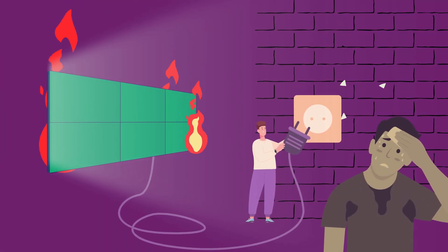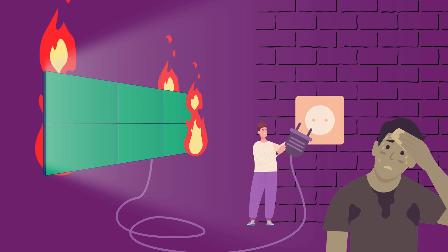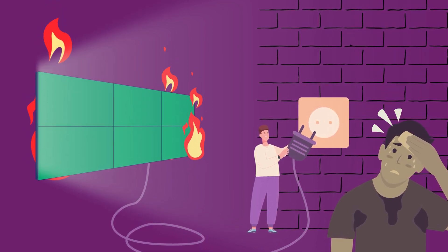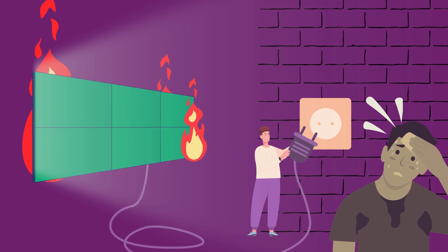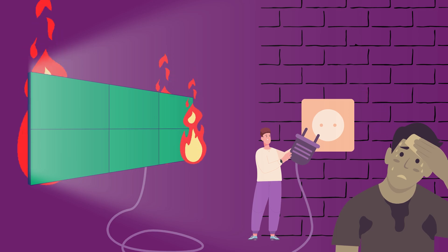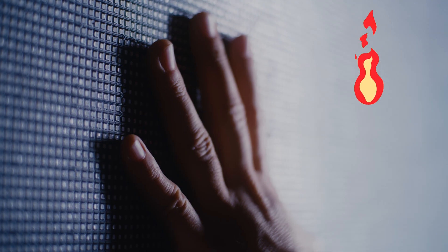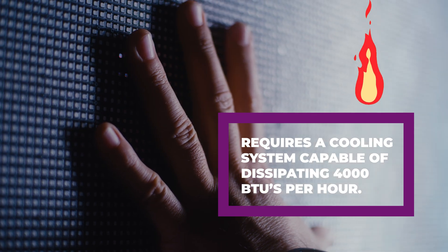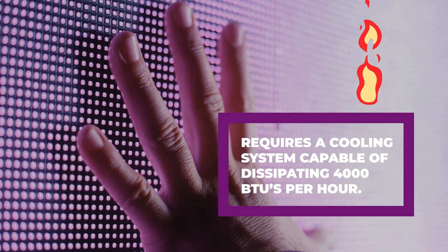Heat, or BTUs. The heat generated by an LED wall depends on its power consumption and the environment where it's installed. The BTU rating measures the amount of heat generated by the display, and it's essential to consider it to ensure the screen doesn't overheat. For instance, an LED wall with a BTU rating of 4,000 requires a cooling system capable of dissipating at least 4,000 BTUs per hour — that's a third of a ton of additional air conditioning for the space.